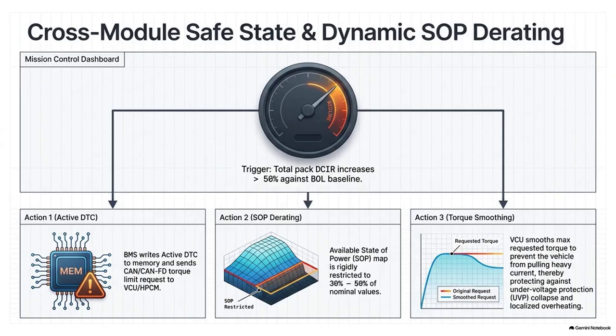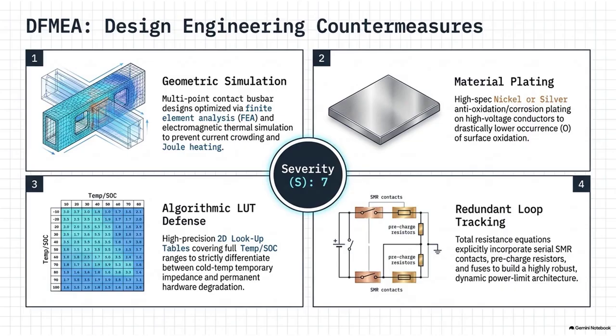And there's an electrical necessity to that smoothing as well, related to the voltage limits, correct? Not just the physical jerk. Yes, preventing an undervoltage protection, or UVP, shutdown. Because the internal resistance is so high, pulling normal current causes the terminal voltage to sag violently. We talked about the voltage sagging earlier.